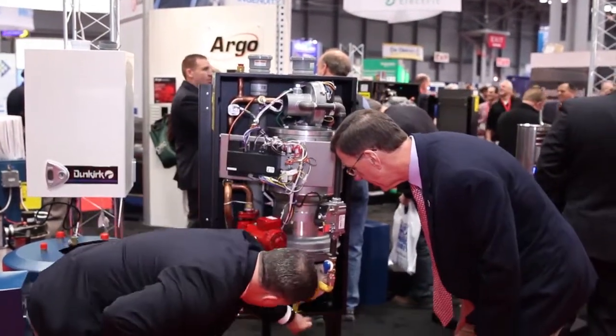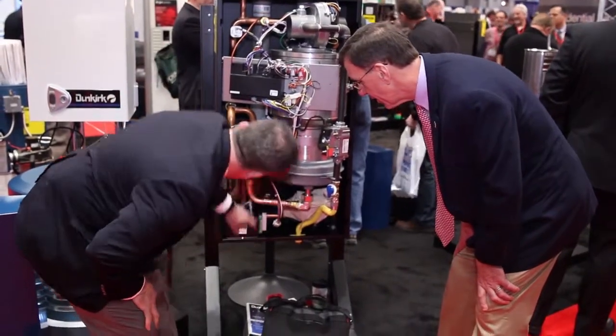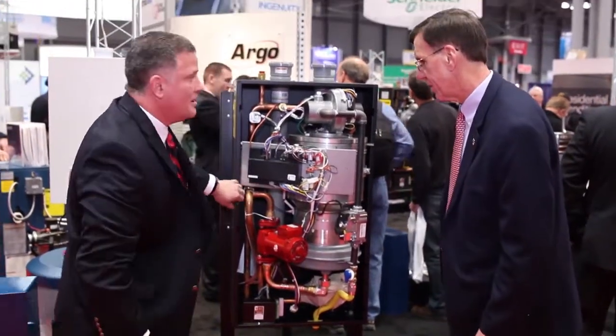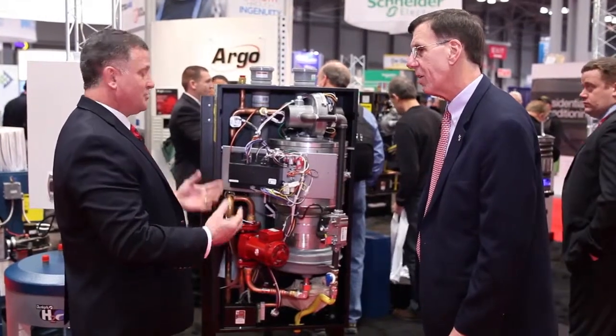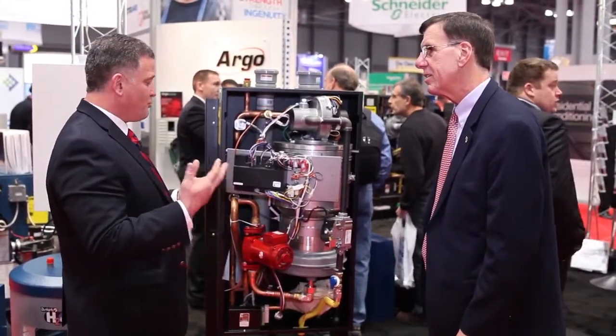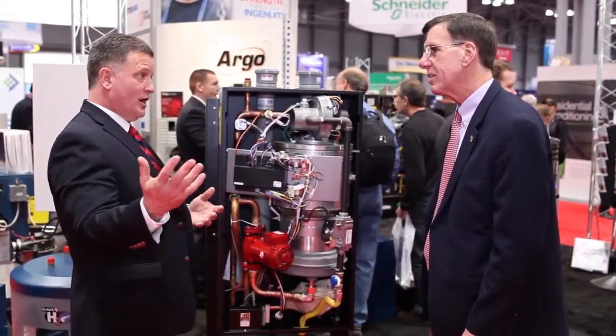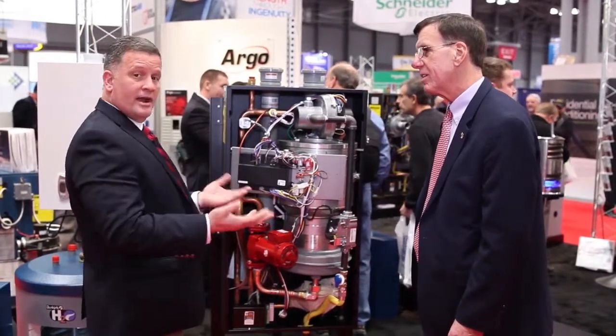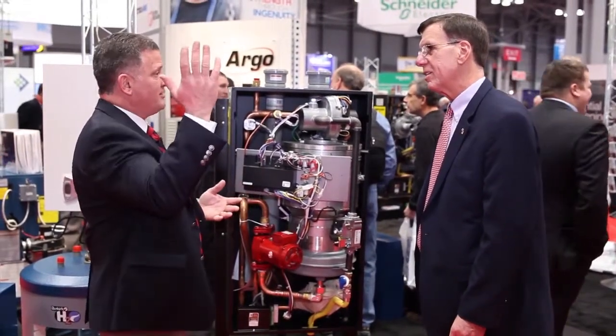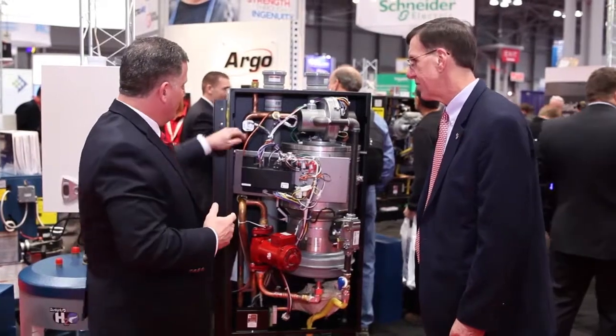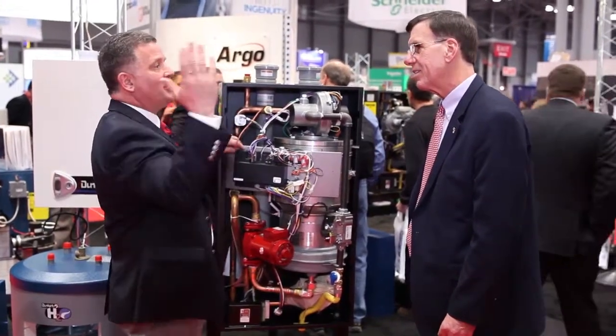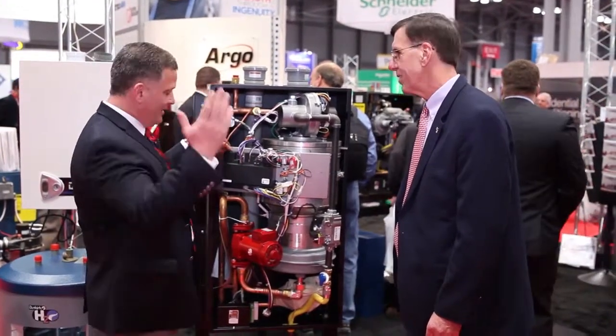So you see, we bring our return pipe in, our supply out, and up here we have this nifty little primary secondary connection. If there's no primary secondary piping on the job, we pipe it regularly. But you might encounter a job where there's primary secondary piping already there - you merely close the ball valve back here, and now you can reuse the existing piping.